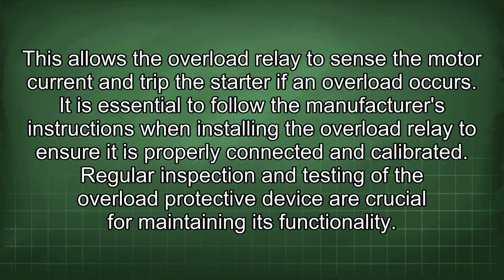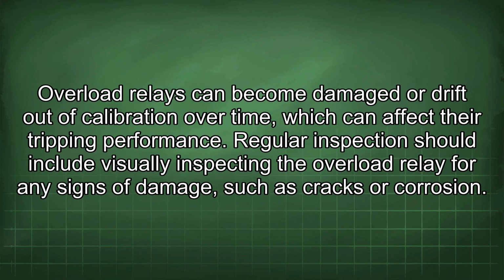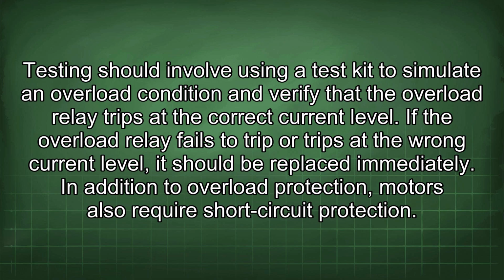Regular inspection and testing of the overload protective device are crucial for maintaining its functionality. Overload relays can become damaged or drift out of calibration over time, which could affect their tripping performance. Regular inspection should include visually inspecting the overload relay for any signs of damage, such as cracks or corrosion. Testing should involve using a test kit to simulate an overload condition and verify that the overload relay trips at the correct current level.